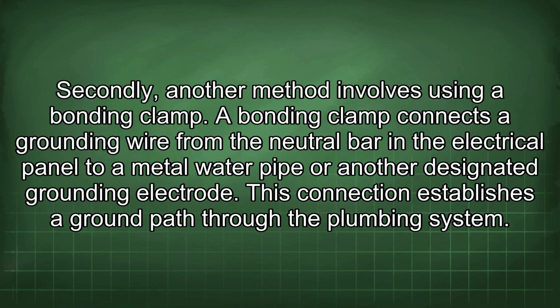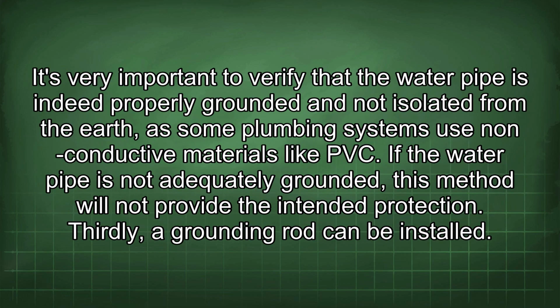Secondly, another method involves using a bonding clamp. A bonding clamp connects a grounding wire from the neutral bar in the electrical panel to a metal water pipe or another designated grounding electrode. This connection establishes a ground path through the plumbing system. It's very important to verify that the water pipe is indeed properly grounded and not isolated from the earth, as some plumbing systems use non-conductive materials like PVC. If the water pipe is not adequately grounded, this method will not provide the intended protection.